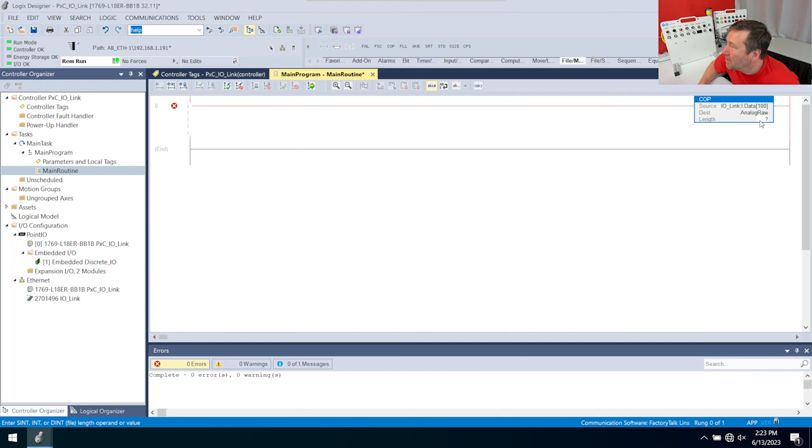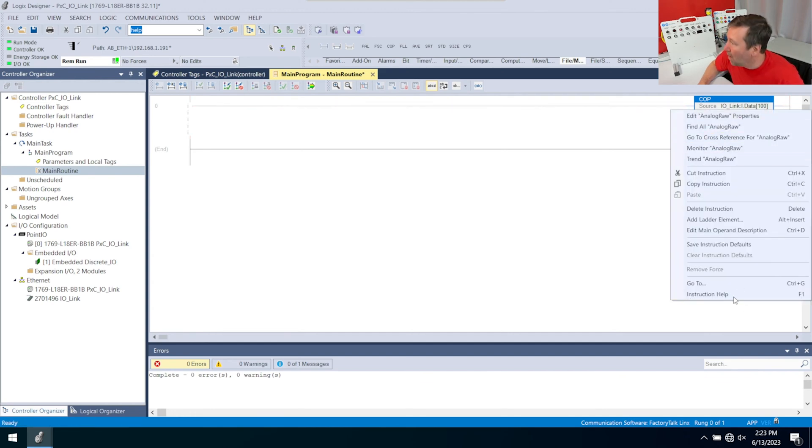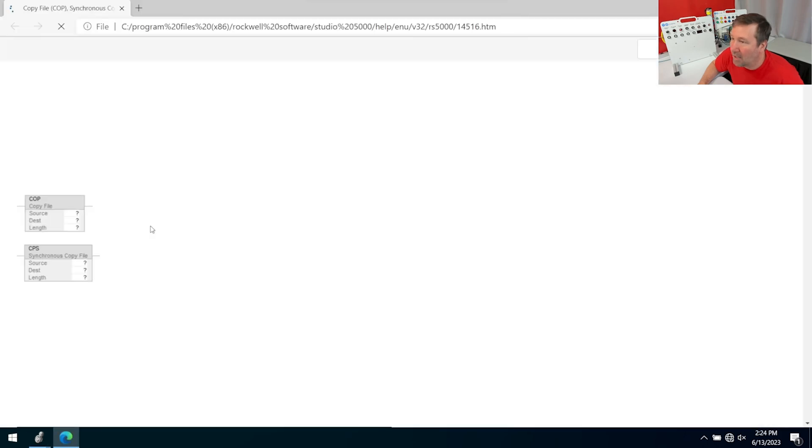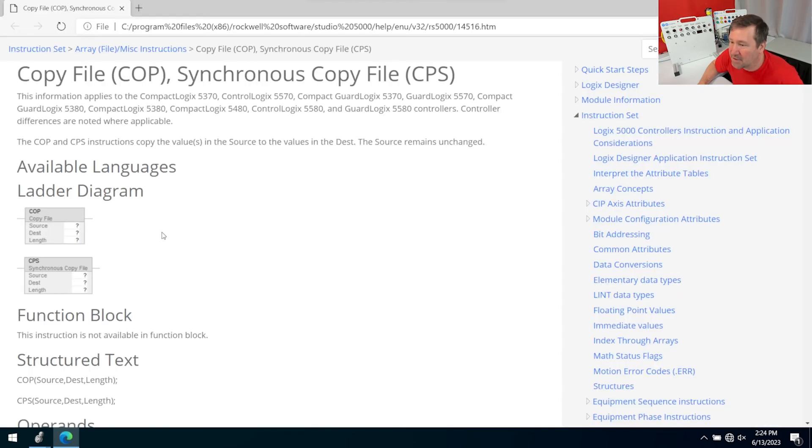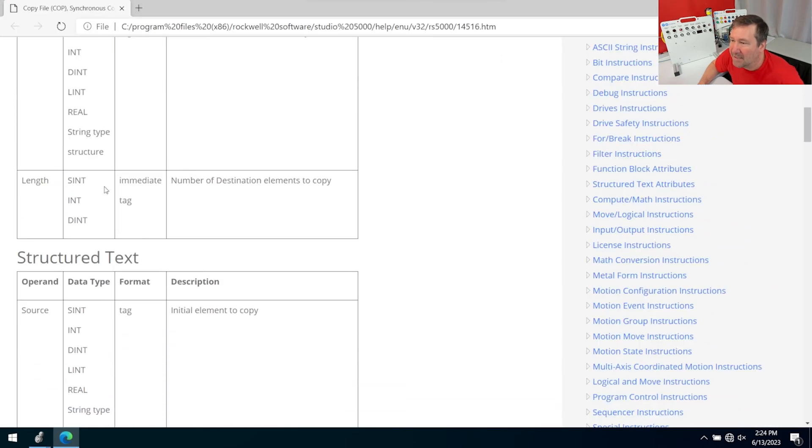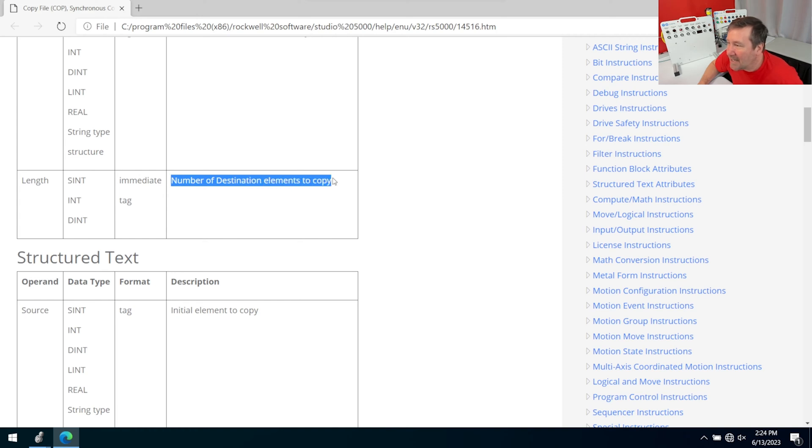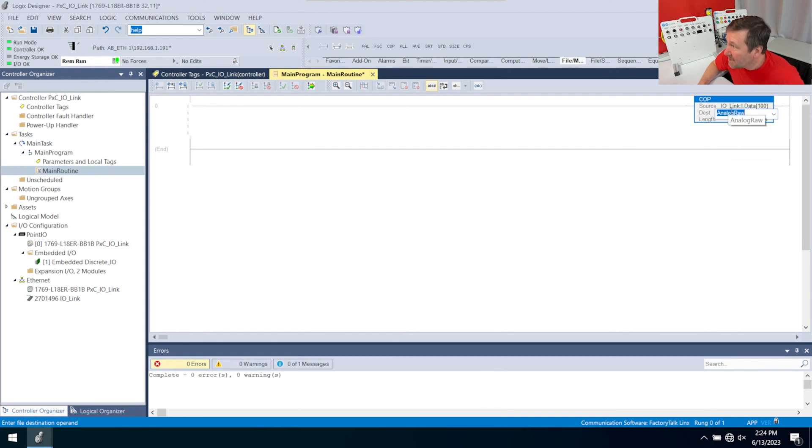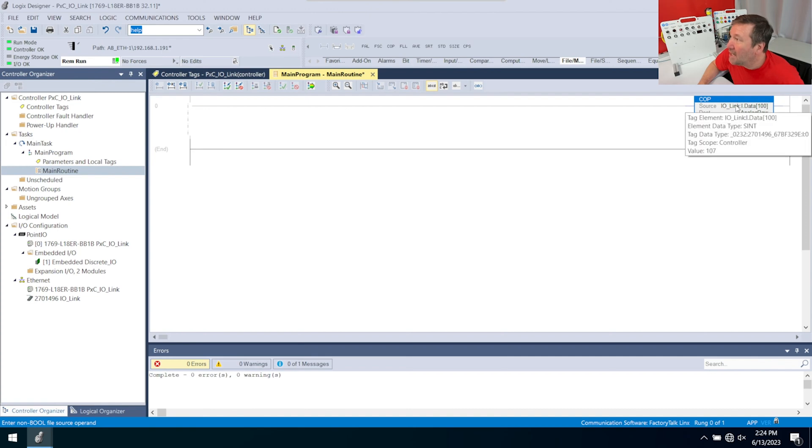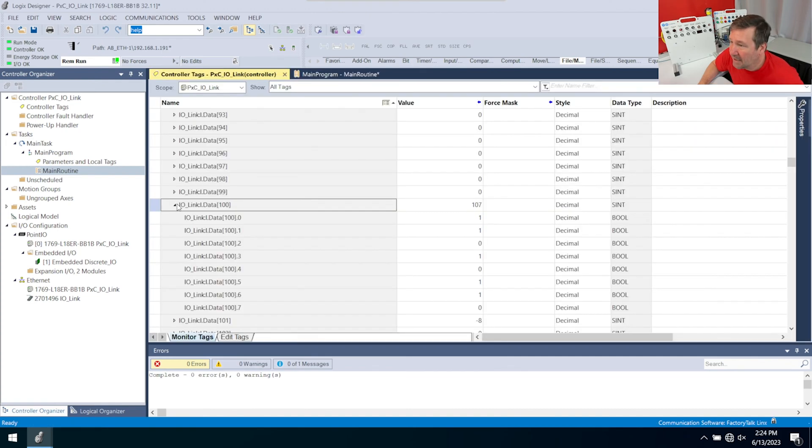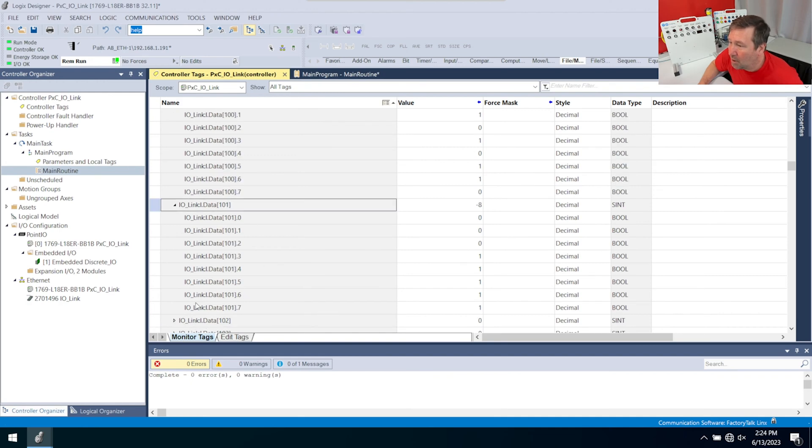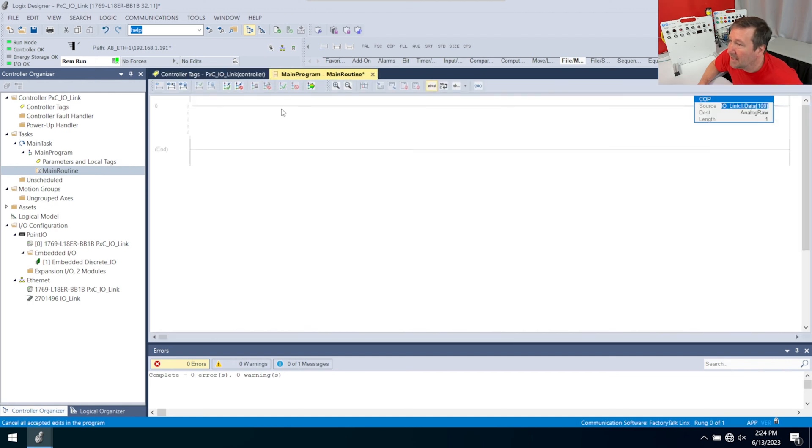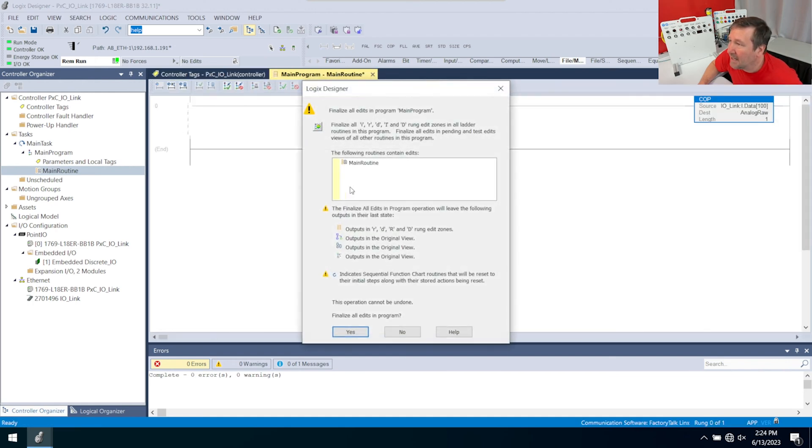Then we're going to do a length of 1. Let's take just a second to understand why we're doing this length of 1. If we go to the instruction help and look at this length, it's the number of destination elements to copy, and that's going to be bit-wise. So since we have 16 bits in our destination and we have a length of 1, that's going to copy 16 bits up here. That's going to get you data 100, 0 through 7, and data 101, 0 through 7. Let's put this in and see what we get.